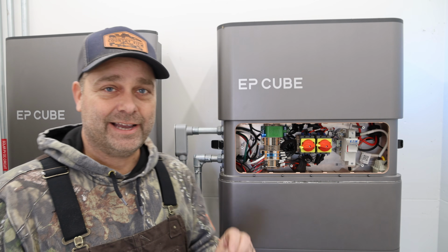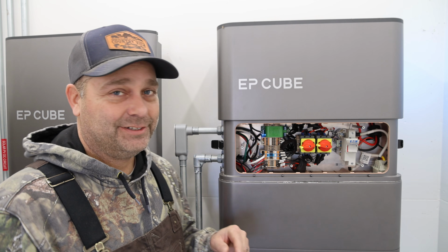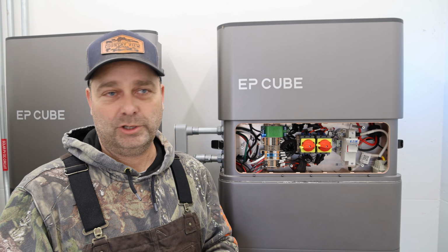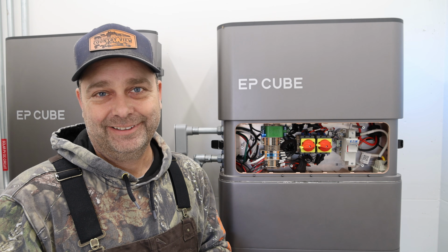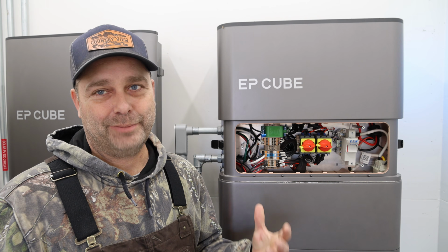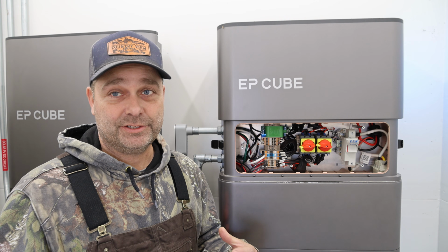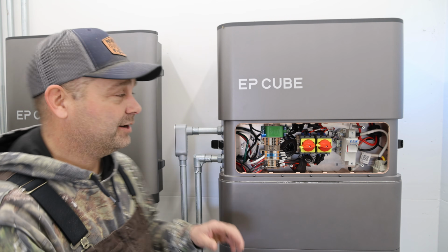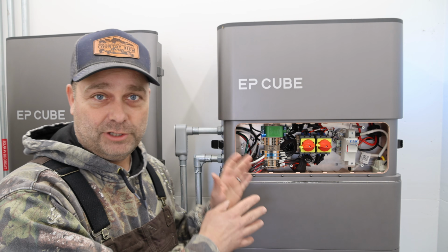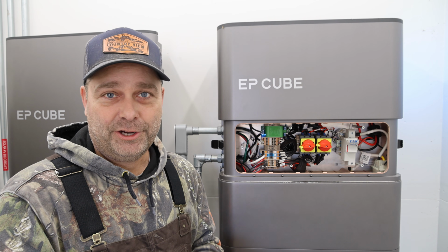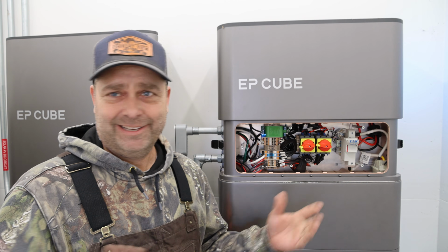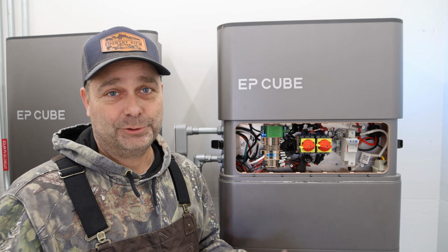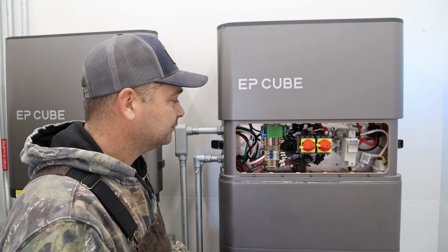So what I did next is I disconnected those arrays. I have 3 different solar power systems, and they all come into this room. So I was able to disconnect arrays 1 and 2, and I wired those over to my 12K PV, turned on the arc fault detection, and it worked perfectly fine on that inverter. There was no problem with the solar panels whatsoever.